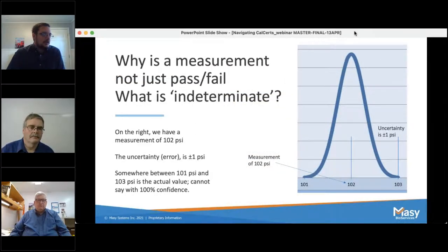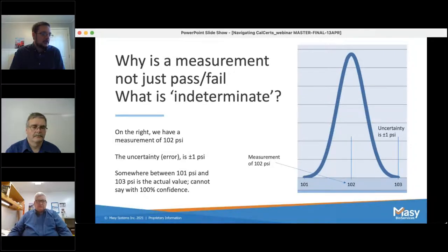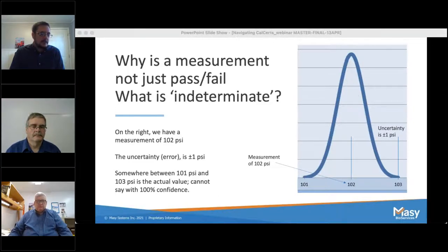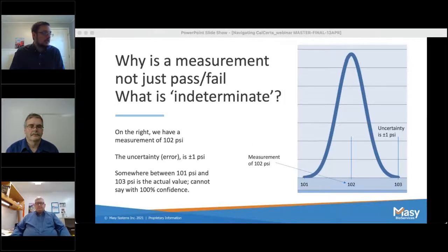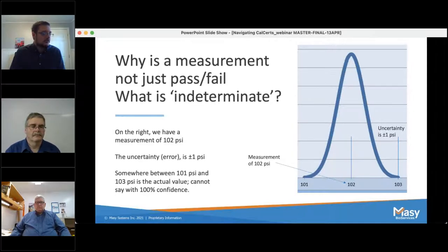In this example using a pressure gauge with a 102 PSI measurement, our uncertainty is plus or minus one. The uncertainty is represented by a bell curve because it's statistical — somewhere underneath this bell curve is the actual measurement. Because of all the uncertainty influences — things like drift, operator error, calibration uncertainty — we do not know with 100% confidence where that true value is, but it's somewhere underneath this bell curve. If the standard was just calibrated yesterday, we might have a better understanding, but six to twelve months down the line, things drift and wear, and all those external influences will shift this around. Until you have that device recalibrated, you won't know where that true value is.